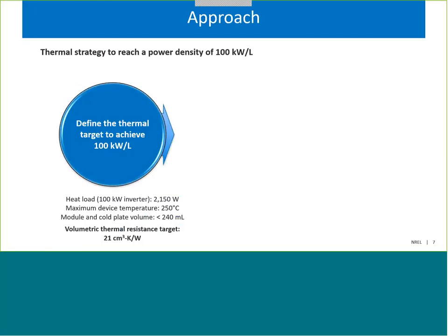This is the approach to develop a thermal strategy to reach a power density of 100 kilowatts per liter. First, we defined a thermal target that would allow us to reach that power density. That thermal target was defined in terms of a volumetric thermal resistance, where the thermal resistance was scaled by the volume requirements for the power module and the cold plate. In this case, the thermal resistance was computed by first estimating the heat load of a 100 kilowatt wide bandgap inverter, which we estimate to be about 2,150 watts.